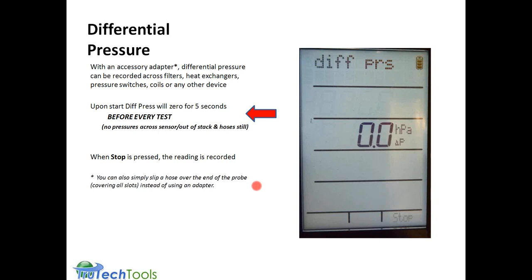Differential pressure, either with or without an accessory adapter, and here's a little star, you can simply slip a hose over the end of the probe, covering all the slots instead of using a pressure adapter. But you could get an accessory adapter to do differential pressure tests to record the pressure drop across filters, heat exchangers, pressure switches, coils, any kind of device.